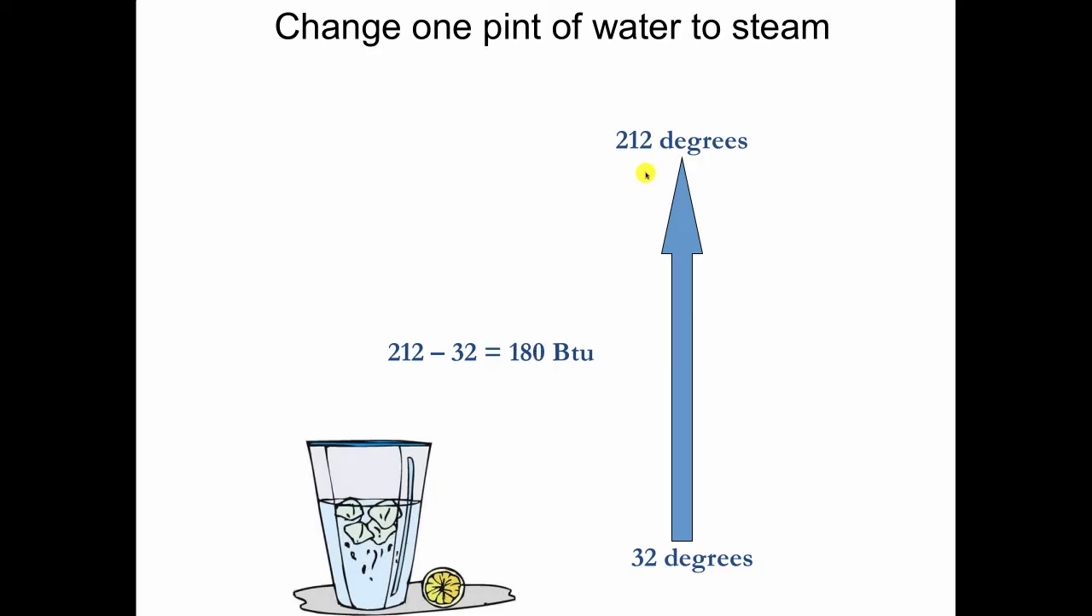But now that's not steam. That's just really hot water, 212 degree water. To get steam, it would be nice if we could throw one more BTU into the pot, one toke over the line and suddenly you got steam. But then a watched pot never boils would not be true. No. To get that pound of water to turn state, to get those little molecules excited enough that they leap off the surface of that water, we have to add a magnificent 970 BTUs per pound. And it's still only at 212 degrees. It's at zero PSI. Now that's the heat that's going to heat the building, right there.